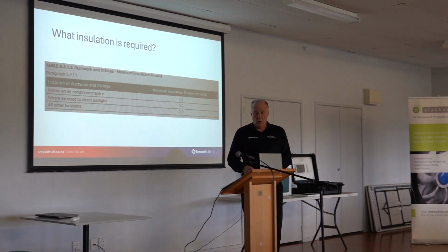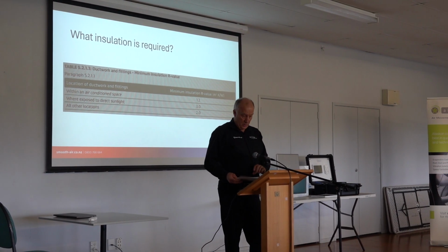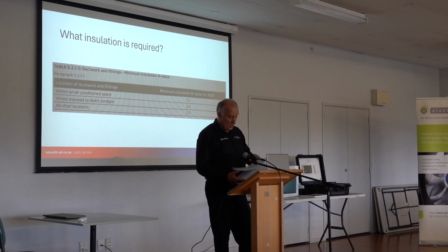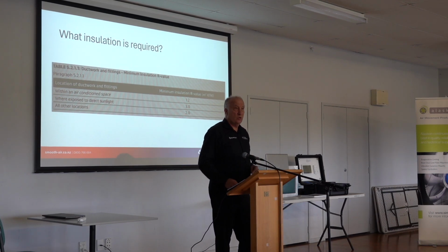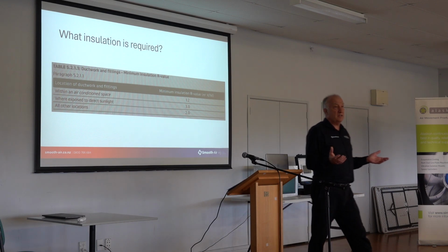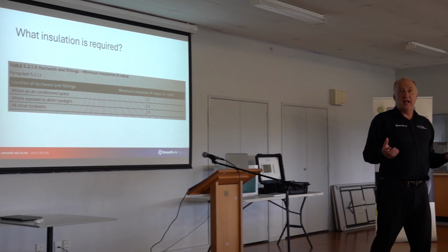So, what does that mean for us, supplying the duct? It means a whole bunch of things. One, there's a whole bunch of additional cost. If you're using galv duct and you're putting insulation on it, to get R1.2, you've got to have a duct wrap of about 50 mil. If you're going R2, it gets up to about 75.